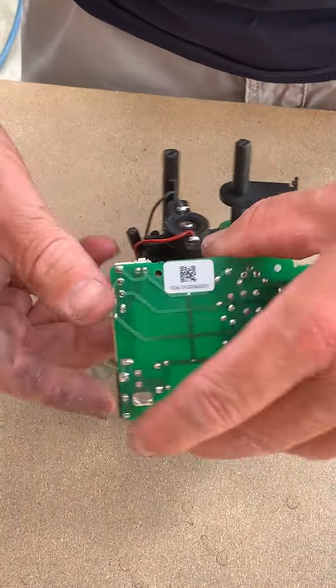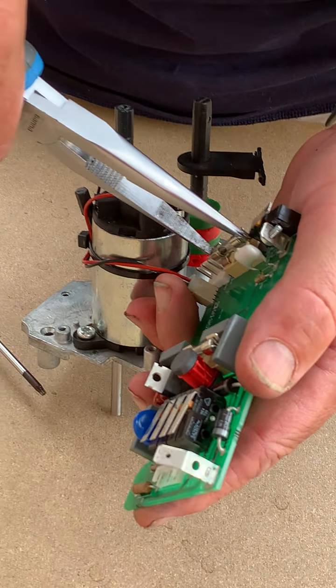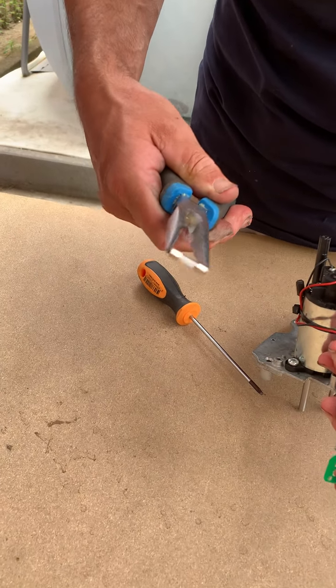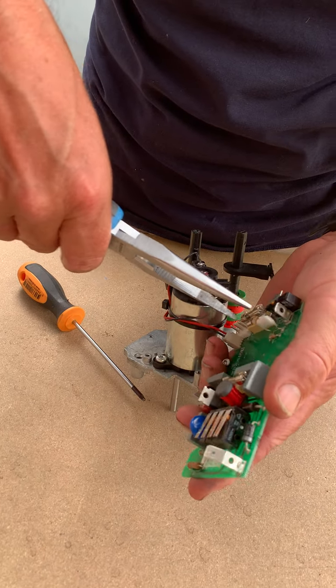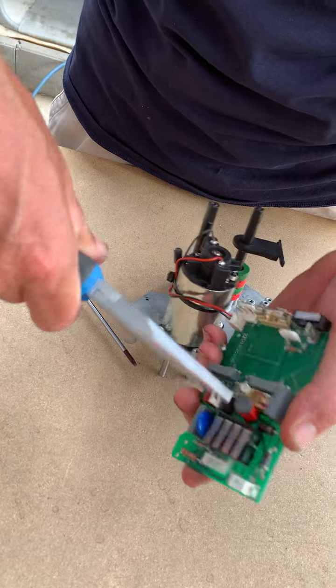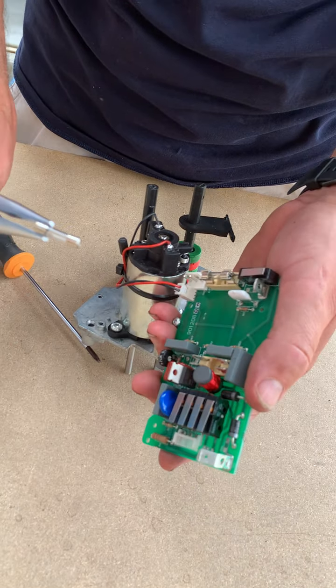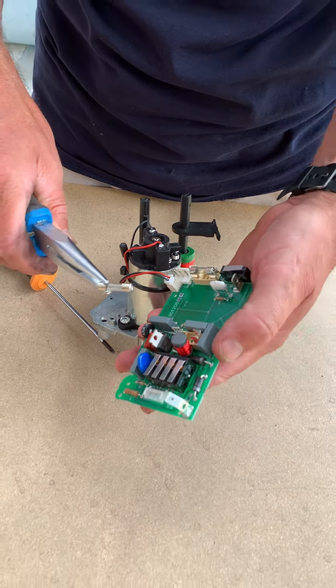You can see there are two fuses which can melt down. These fuses melt down in case the motor is too tight or the ball valve has been tightened too fast or not greased.